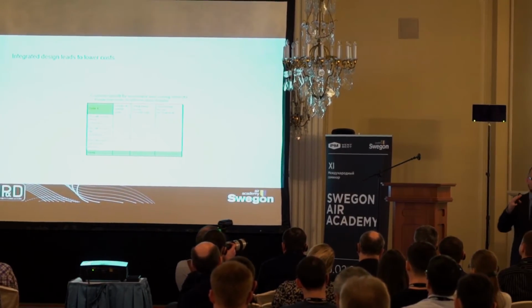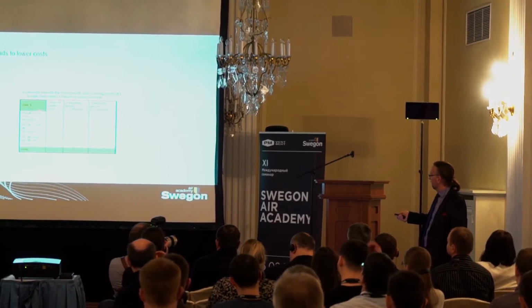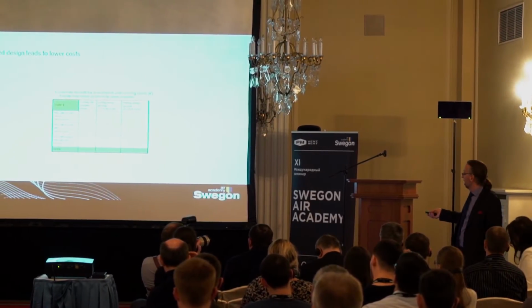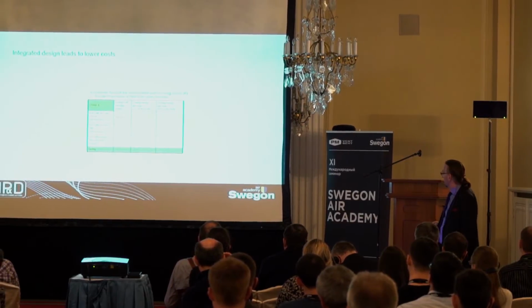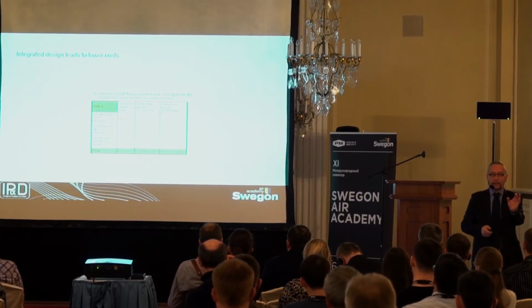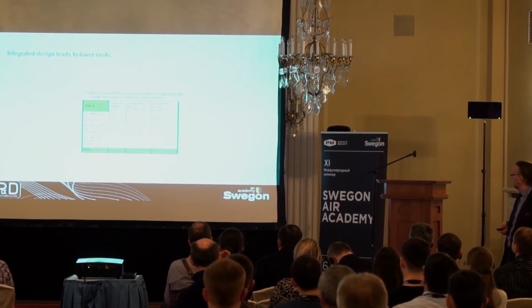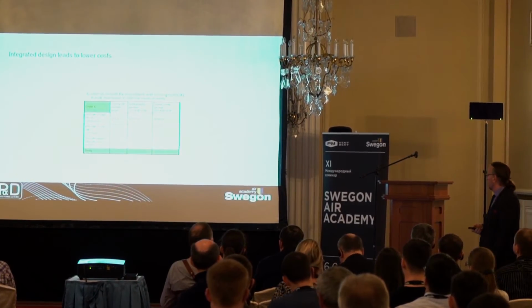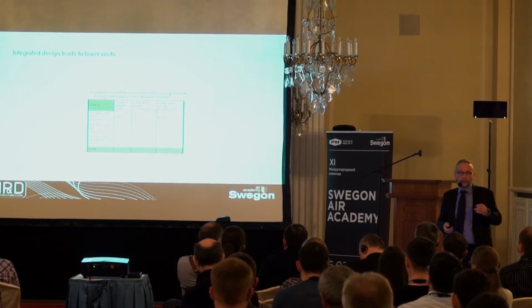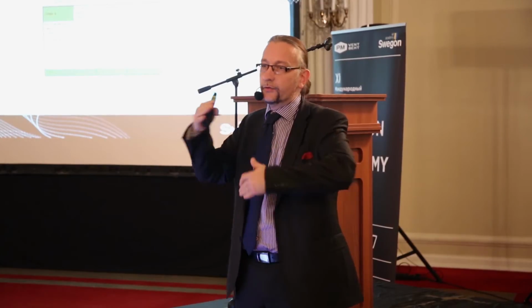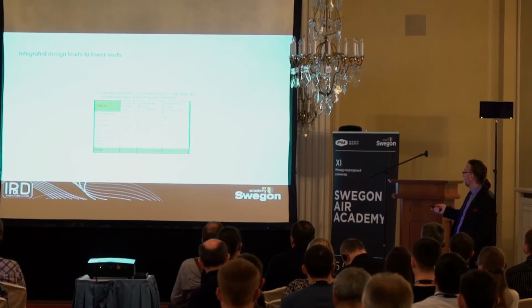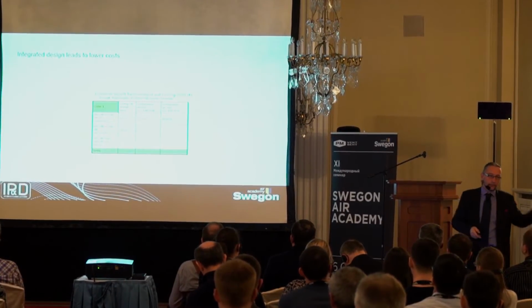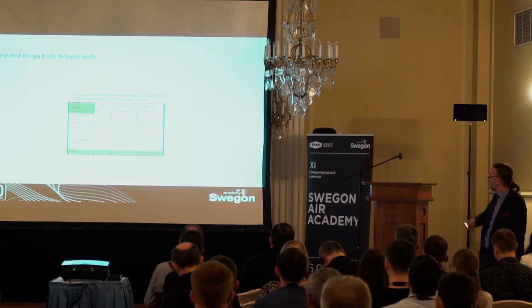If you go to an air handling unit and you integrate the different components inside an air handling unit, we're talking about the rotor only and about cool recovery. Now we compare an air handling unit with a standard rotor and without cool recovery. And you will see that here you will need, in Rome, Italy, a big unit, you need to install a cooling battery of 400 kilowatt. So you need a chiller that takes care of 400 kilowatt. And the running cost for a DCV or a VAV system per year is accordingly. Now, as soon as you have cool recovery, so you actually use that the indoor air is colder than the outdoor air, so you pre-cool the air with the extract air, this number goes down to about 300 kilowatt, so 1/4 down. And of course, the energy use per year goes down as well.